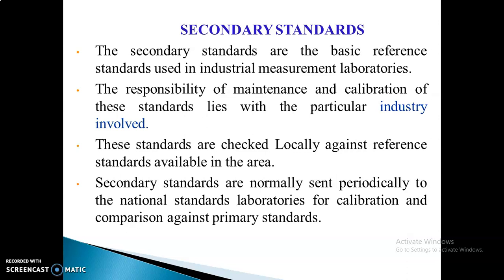These standards are checked locally against a reference standard, and the secondary standards are normally sent periodically to the National Standard Laboratory for calibration. Only then are these particular standards valid.